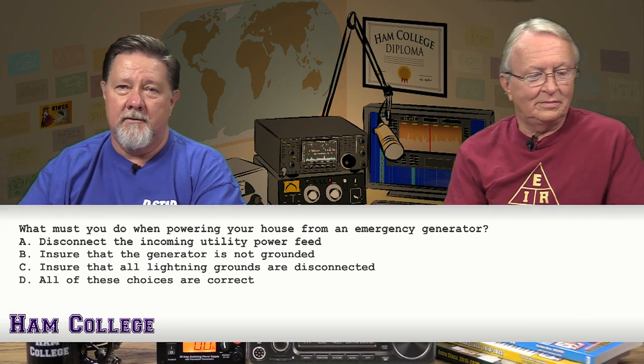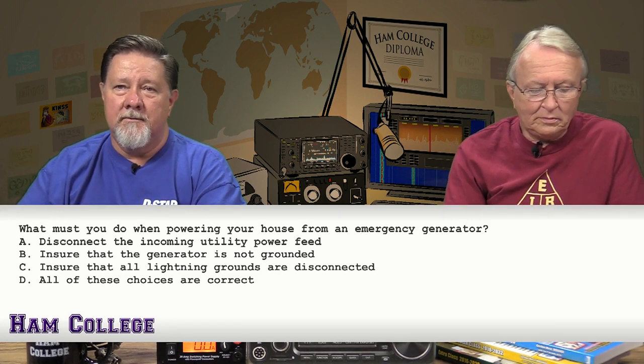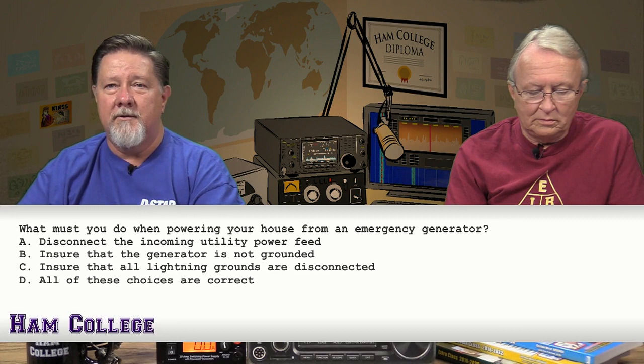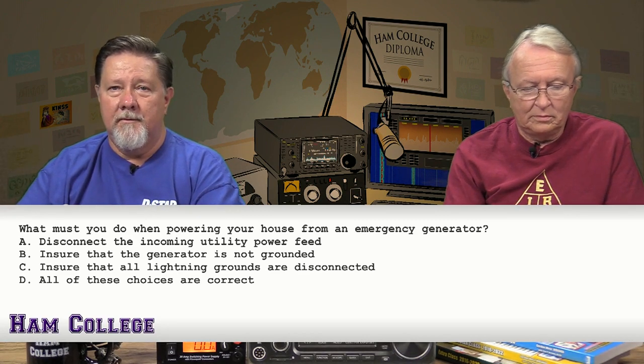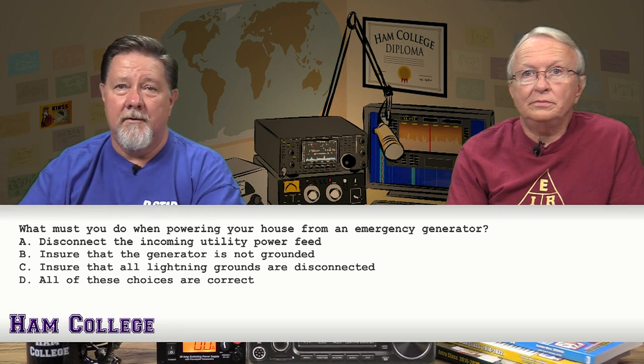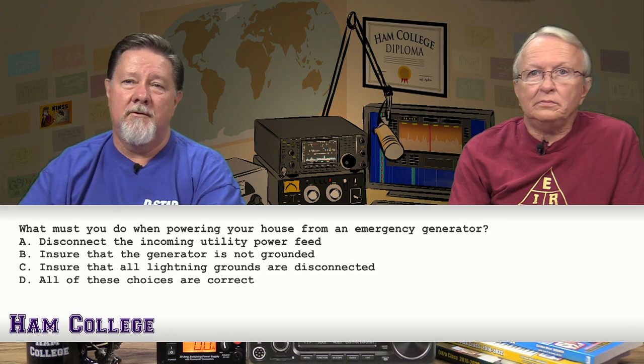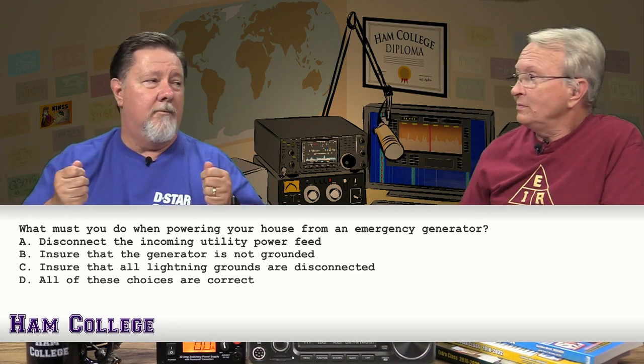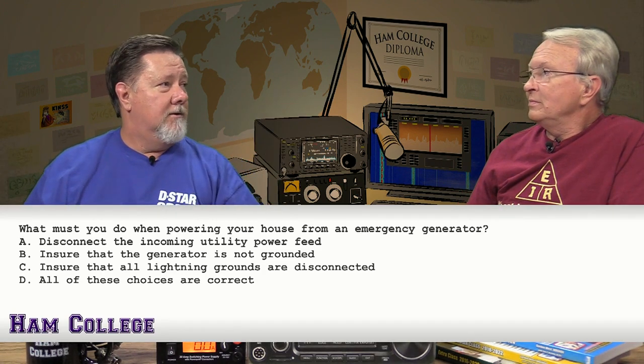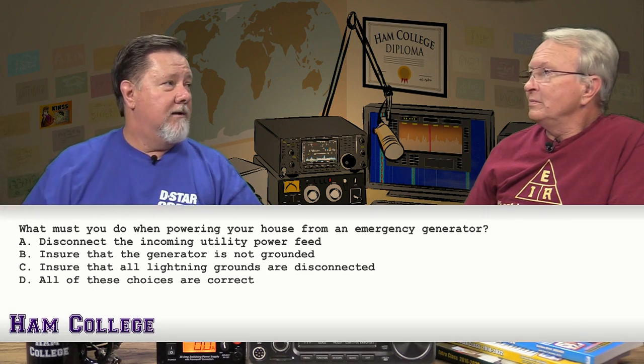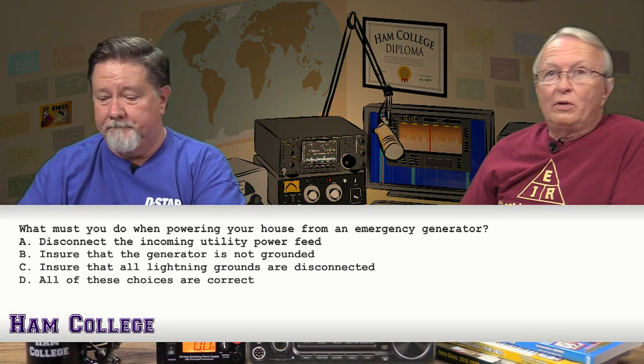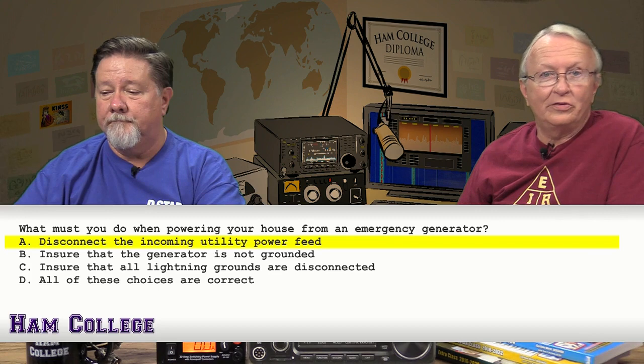They're not all correct. You don't want to ensure all lightning grounds are disconnected. And ensuring the generator isn't grounded isn't right either, it's perfectly fine to ground the chassis of your generator, though I don't ground mine. Disconnecting the incoming utility power feed is the answer, because if you hook your generator output to your house circuit, it can backfeed into the power lines. If the power comes back on, you could get a heck of an explosion, or backfeed through the lines and shock someone else in their home, causing damage. There would also be quite a load on your generator. You definitely want to make sure the incoming utility power is disconnected.